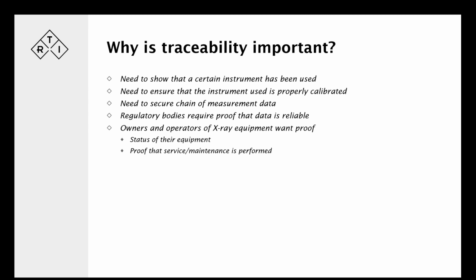There's also, if they outsource the service and maintenance, even if it's maintained in-house, this could serve as proof that the service and maintenance is performed, and to document that and keep that document for future reference. And to have that documentation valid, of course, it survives better if we can prove the traceability, if there is traceable data in those documentations. So, of course, that's the whole idea behind it.